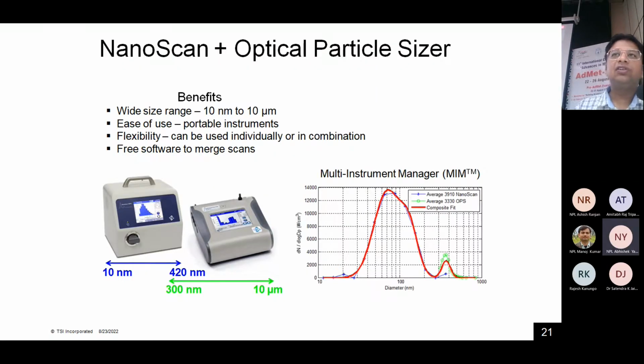Then one of the other solutions we have at TSI is the NanoScan plus OPS. Basically, these are two different equipments, but we can combine them to give you an entire range. The NanoScan, which is a small portable equipment, can give you data from 10 nanometer up to 420 nanometer. It's based on electrical mobility. And then we have the optical particle sizer, OPS, which goes from 300 nanometer to 10 micron. So if you combine these two ranges, we get 10 nanometer up to 10 micron as a full range.